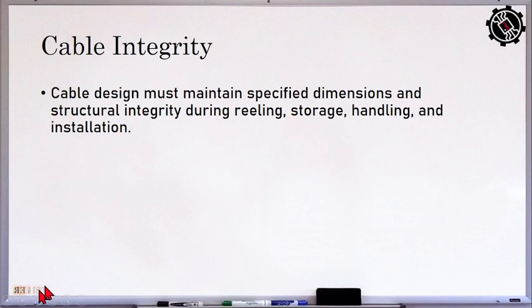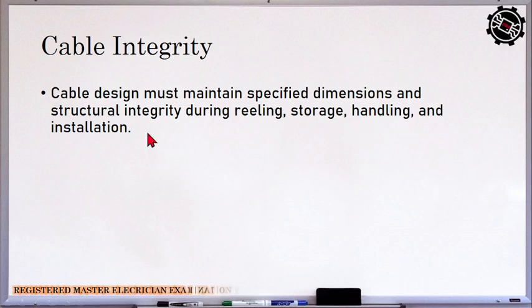So cable integrity. Cable design must maintain the specified dimensions and structural integrity during reeling, storage, handling, and installation. So the strength of the cable, its dimensions and sizes, must be maintained during the reeling. So if nasa reel pa siya o nasa roll, tapos naka-store, handling and installation. So dapat during the reeling na nasa reel pa siya, walang damage doon sa insulation. When it comes to the storage, pag labas na sa storage, dapat walang damage. It is now transferred, that's now handling, to the specific part kung saan siya i-install, so dapat wala pa ring damage. And during the installation of that cable, wala ding damage.